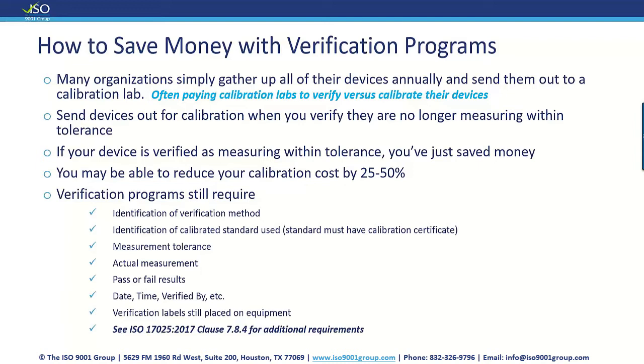So the only time we should be sending devices out for calibration is after you verify that it's no longer measuring within tolerance. If your device is verified as measuring within tolerance, all you have to do is implement a verification program, document all the things that you would typically see on a calibration certificate, and you've just saved your company a lot of money on an annual basis. You may be able to reduce your calibration costs by 25, up to maybe even 50%.